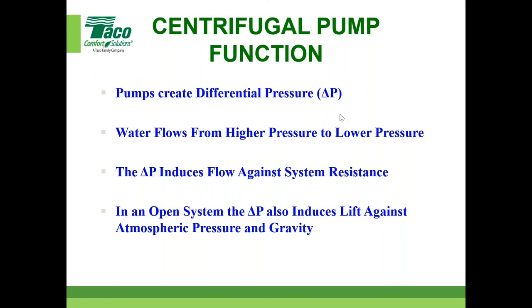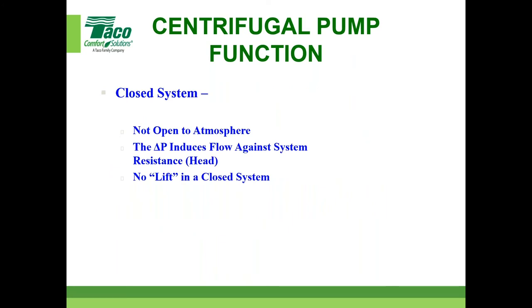So we like to clarify that. Is that a pump fundamental? Well, it's a pump calculation fundamental. So we like to clarify that to make sure everyone understands. So again, a closed loop system, that heating system. You have a boiler in a mechanical room, a chiller located outside, a cooling tower, or whatever. Let me forget the cooling tower right now. Or a heat exchanger, right? A chiller is attached to a heat exchanger. That's a closed loop system. The boiler is attached to some fin tube, some radiation, an air handler, or whatever. The chiller can be attached to air handlers. These are closed loop systems. No lift in a closed loop system. To calculate system resistance, it's the pipe length and fittings and the boiler itself, the chiller itself, and all kinds of different items that the water has to get pushed through, but it's not the lift per se. If there's 100 feet of pipe up and 100 feet down, you have to include 200 feet of pipe, but not the lift itself. So just keep that in mind.